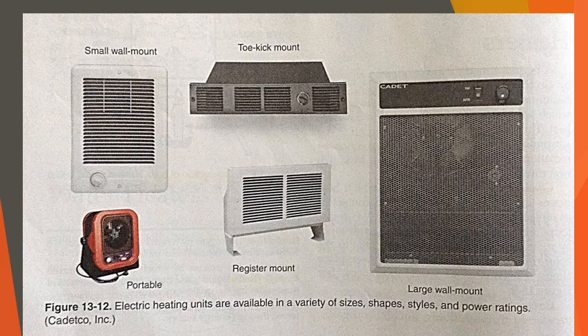Types of heaters. Some heating units are available in a great variety of shapes, sizes, and power ratings. Units may be square, rectangular, or circular. The heater size has traditionally been given in watts or kilowatts of power used. The NEC specifies that heaters have a nameplate that states the size of the heater in either volts and watts, or volts and amperes. These units may range in size from 750 watts or 750 VAs to more than 7,500 watts.